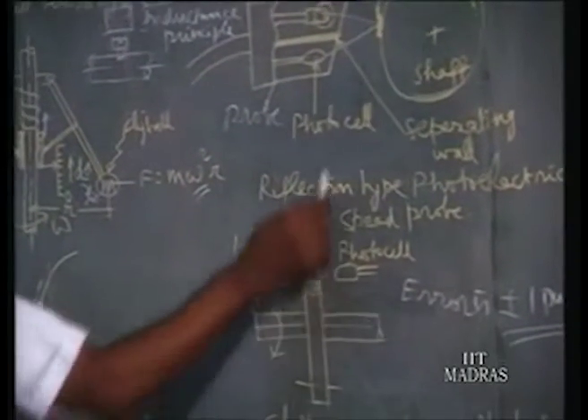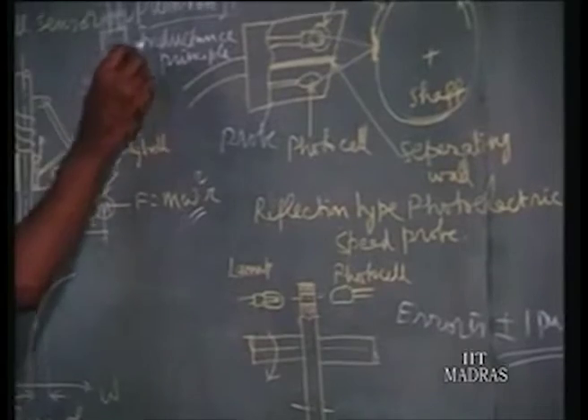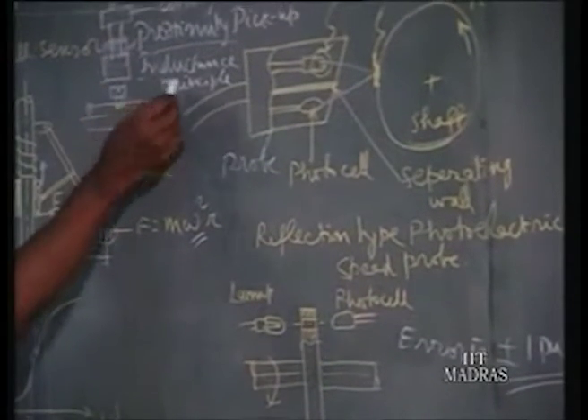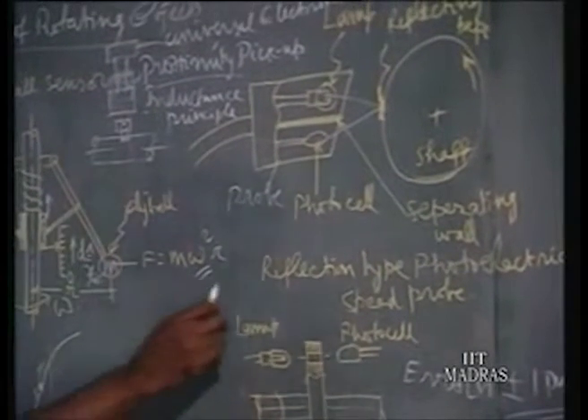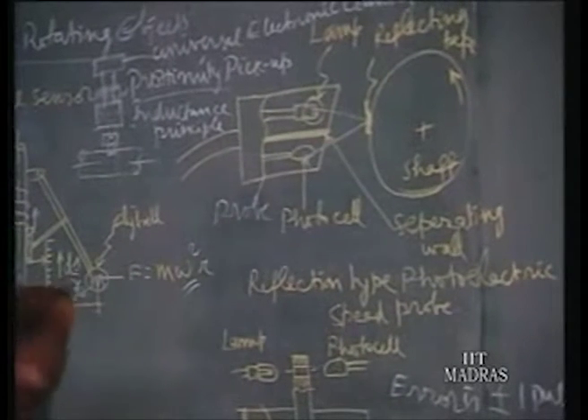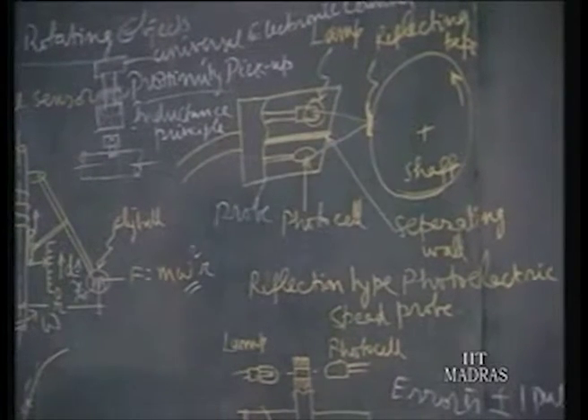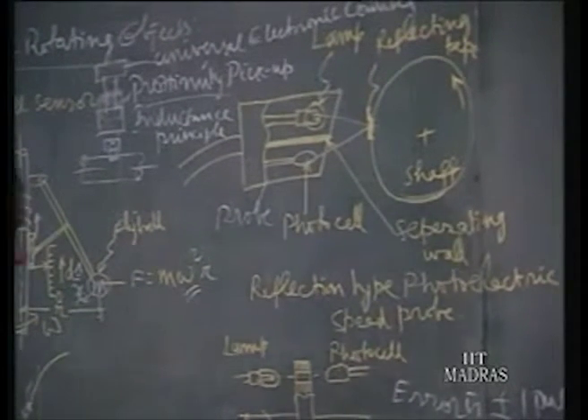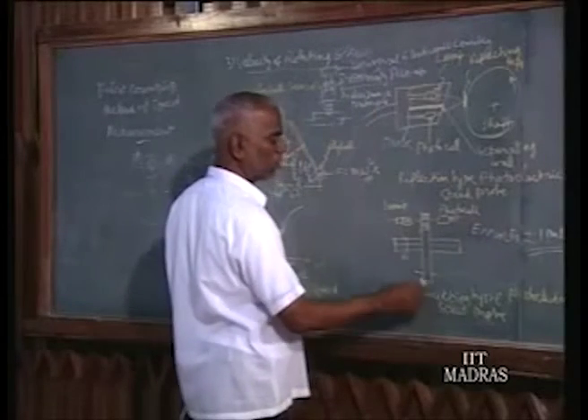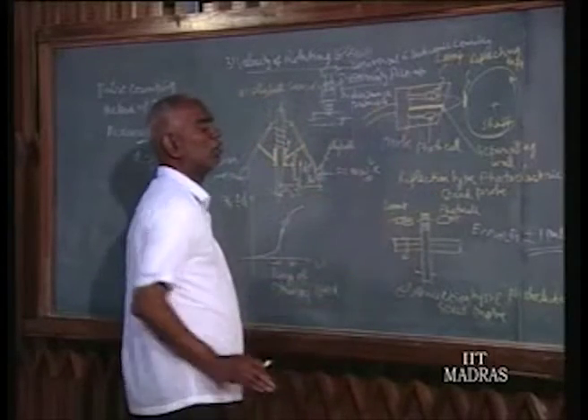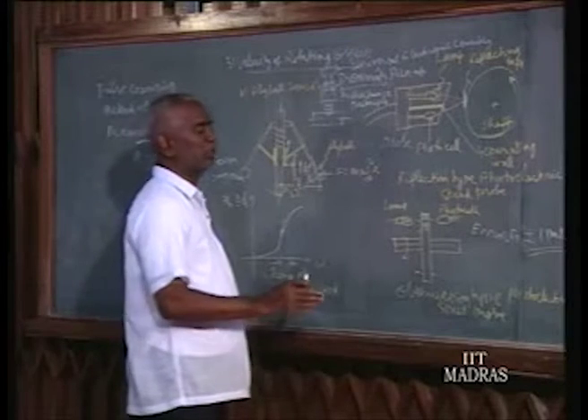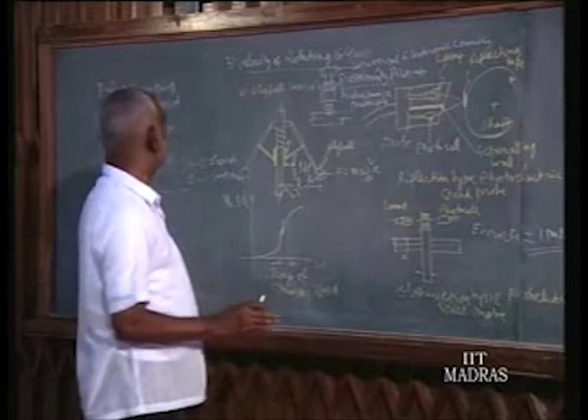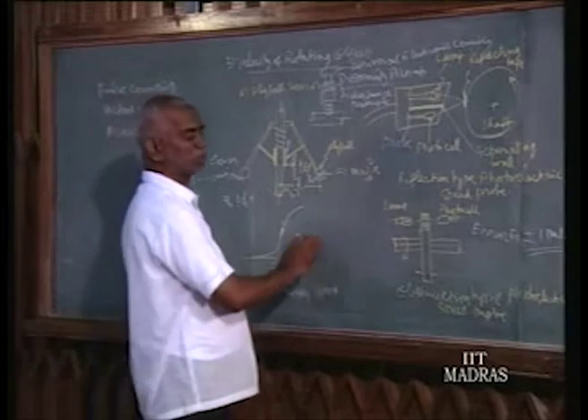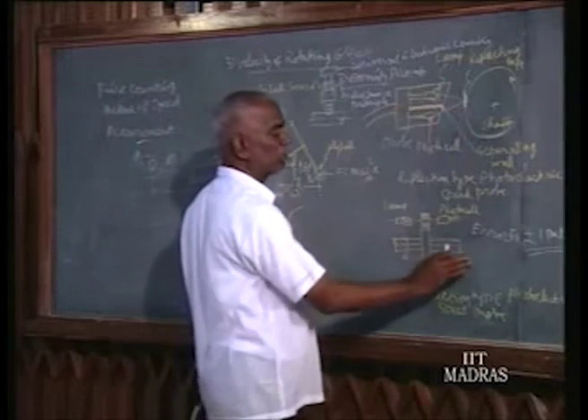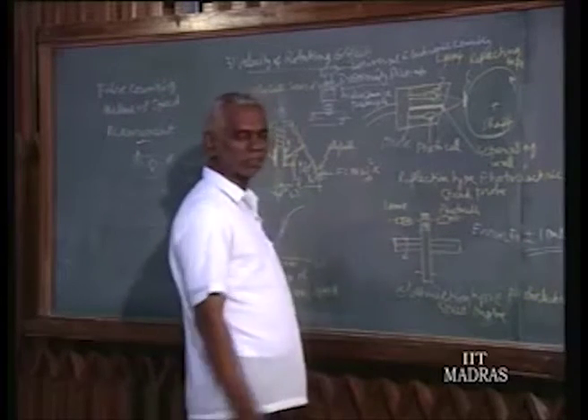In such measurements, whether using the proximity pickup with the inductance principle or reluctance variation, or the reflecting type of photocell, or this one, which we call the obstruction type of photoelectric speed probe, all these are part of the pulse counting method of speed measurement. The error in all these methods is plus or minus 1 pulse.